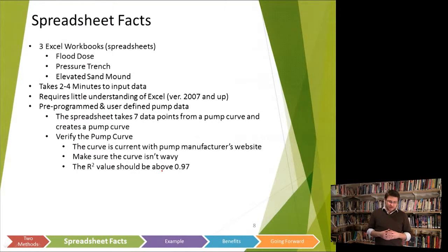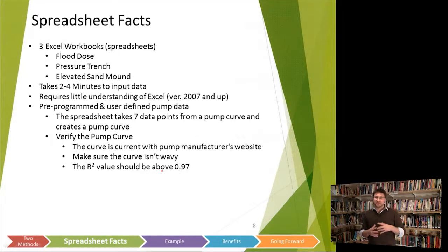With that said, though, I would caution everyone to verify the pump curves. I would verify it to make sure it's current with the manufacturer's pump curve that's listed on their website. Another thing you'll want to do is make sure that the curve that's shown on the spreadsheet isn't wavy. And you'll see most of these curves look very smooth. If there's one that looks wavy, then I would ignore that or not use it.